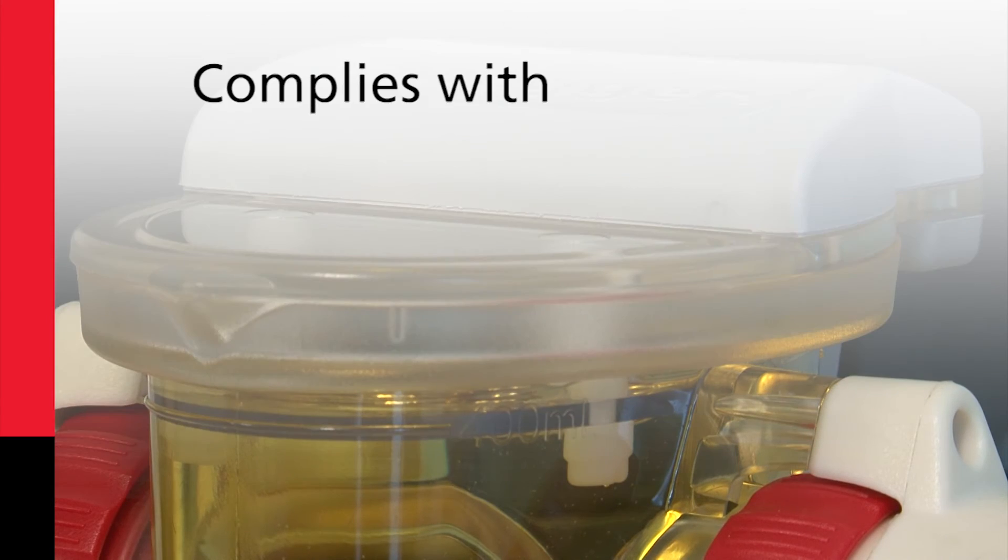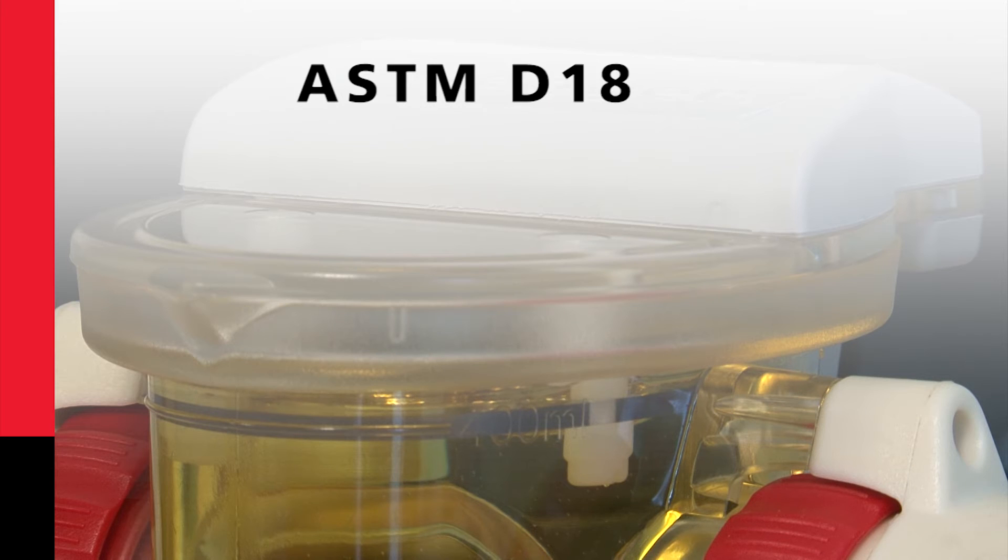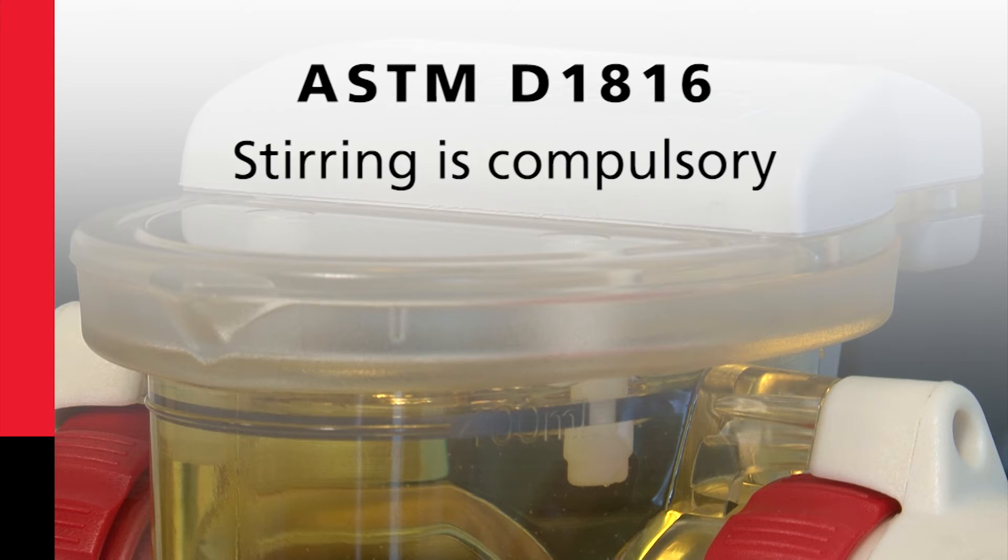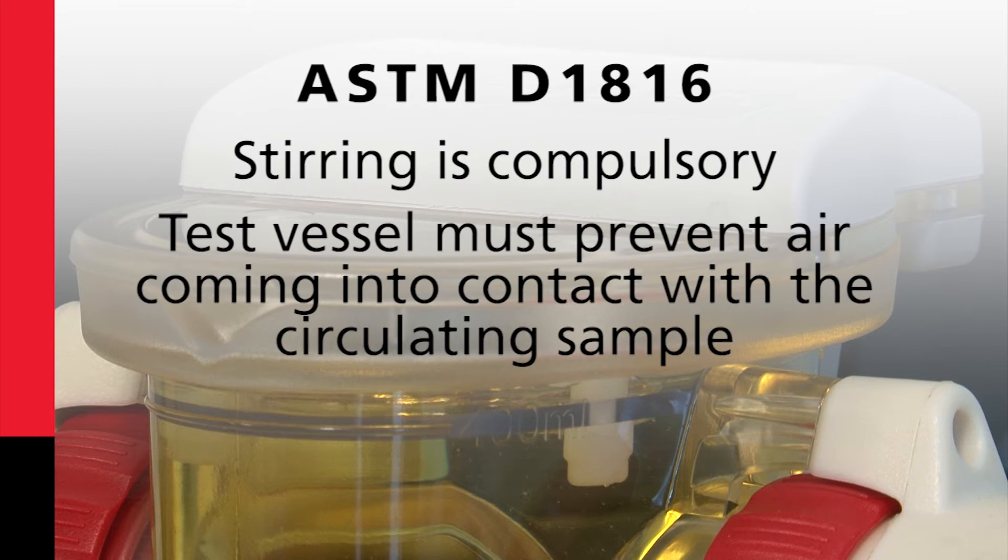This complies with standards such as ASTM D1816 where stirring is compulsory and where the test vessel must prevent air coming into contact with the circulating sample.